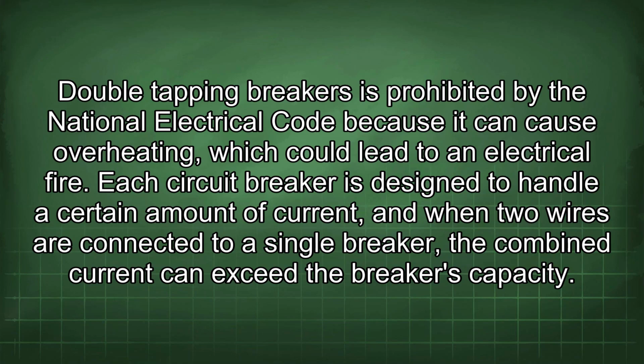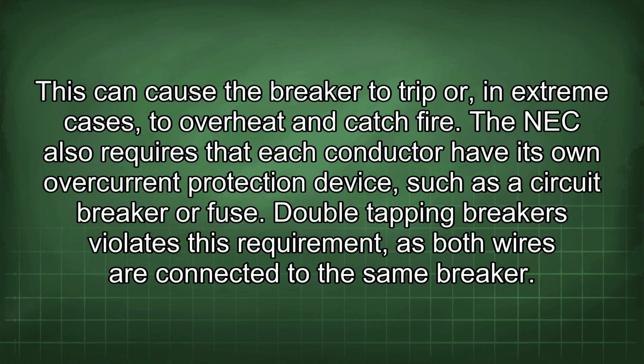Double tapping breakers is prohibited by the National Electrical Code because it can cause overheating, which could lead to an electrical fire. Each circuit breaker is designed to handle a certain amount of current, and when two wires are connected to a single breaker, the combined current can exceed the breaker's capacity. This can cause the breaker to trip or, in extreme cases, to overheat and catch fire.